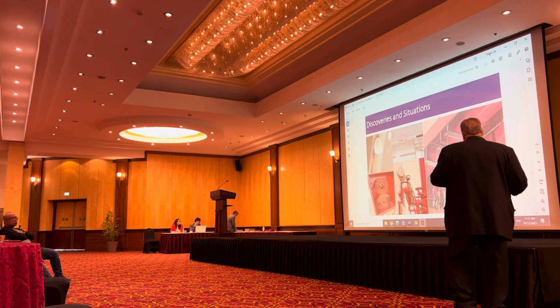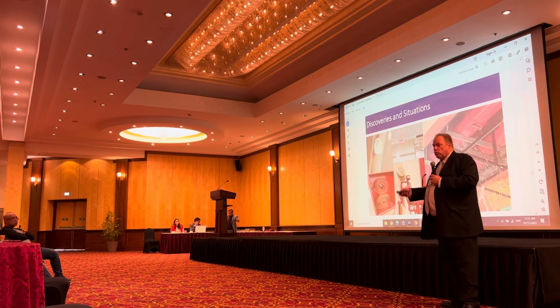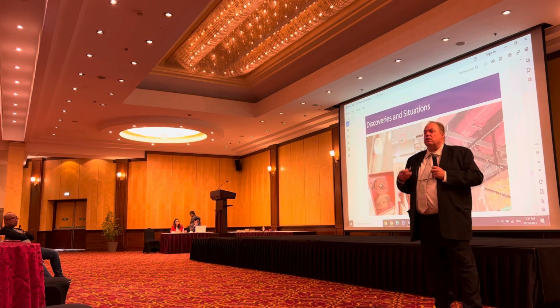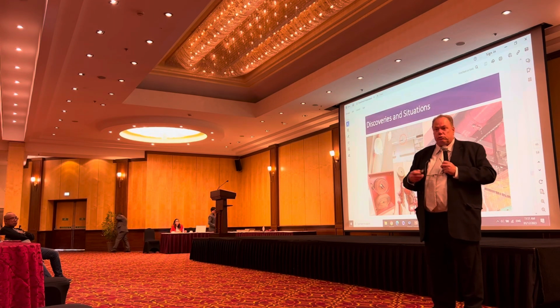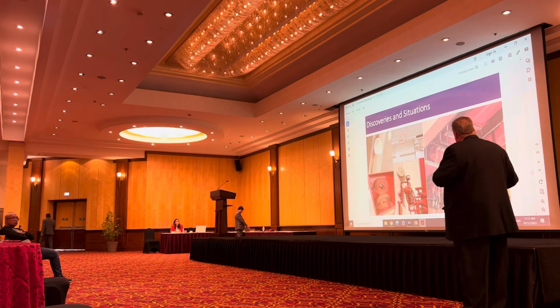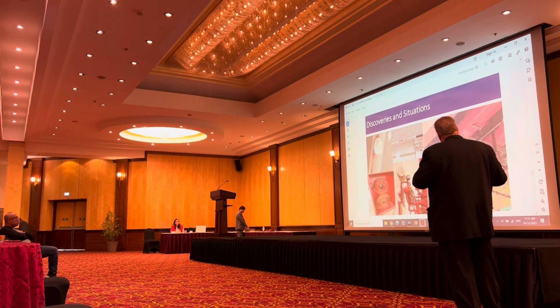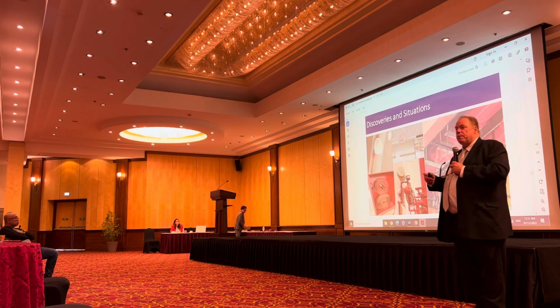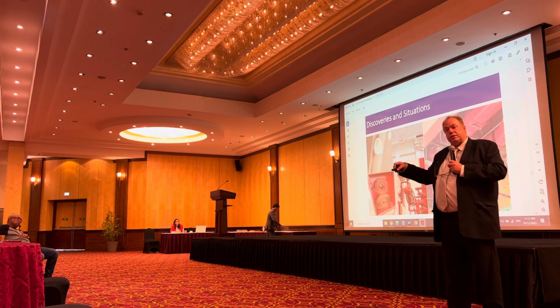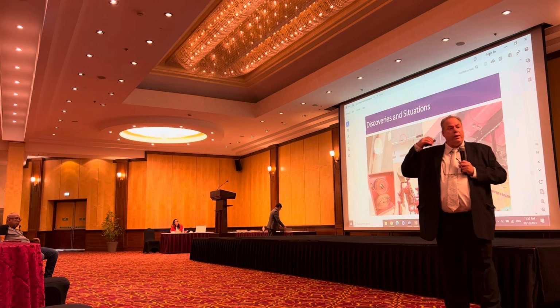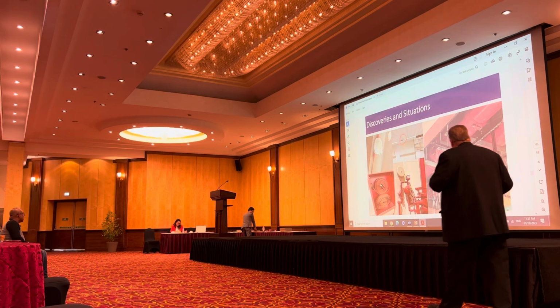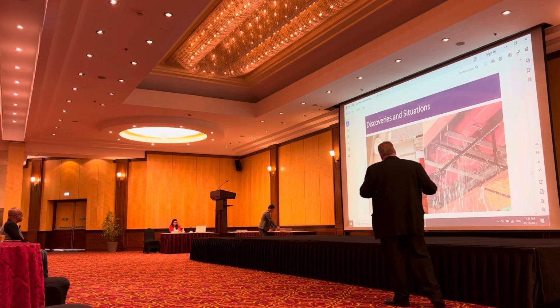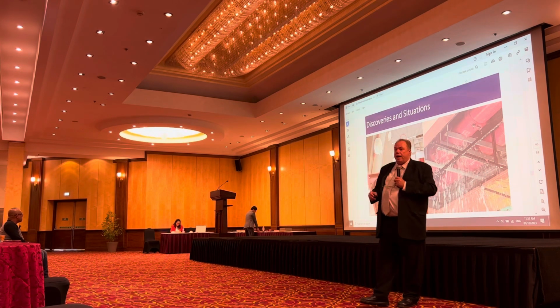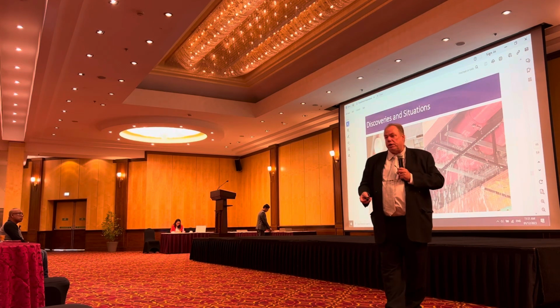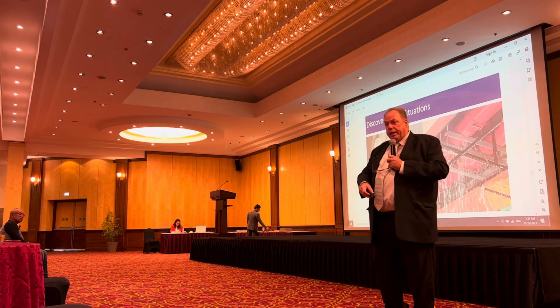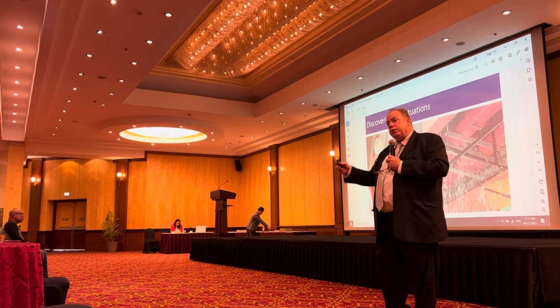Here, a gasket failed on the sprinkler system. Nobody did anything wrong - it's a very difficult climate to work in, it gets very hot, things dry out, gaskets and whatnot. Once we figured out this one failed, the other end of the pipe, we did a second gasket, and after that we came up with a capital project to start replacing all the gaskets in the system. This is critical equipment we can't afford to have downtime on. So it happens. Now we also had to implement a fire watch as per NFPA because we had a compromise in suppression. We had to shut something off to drain it, put the new gaskets in, and recharge it, and that takes time.